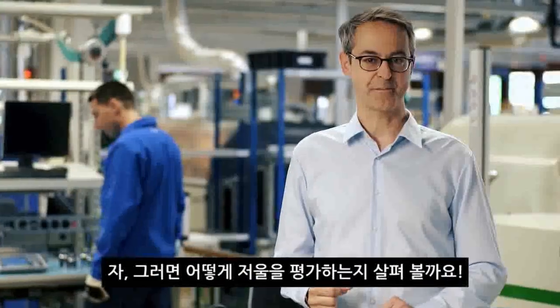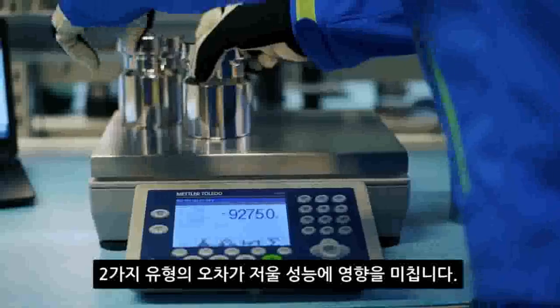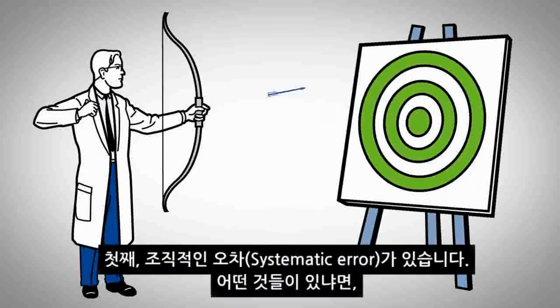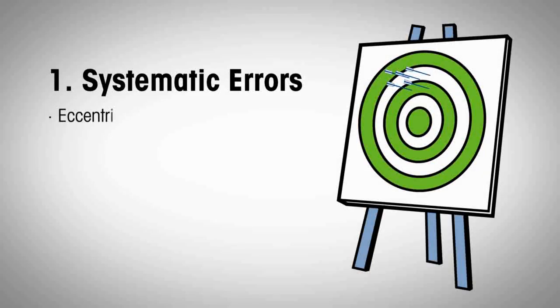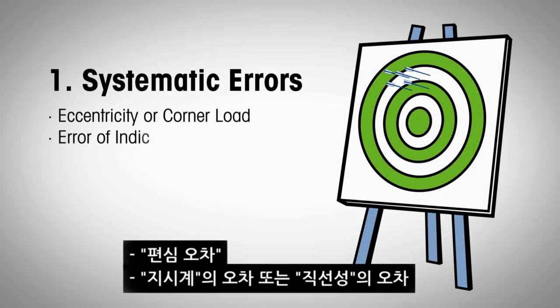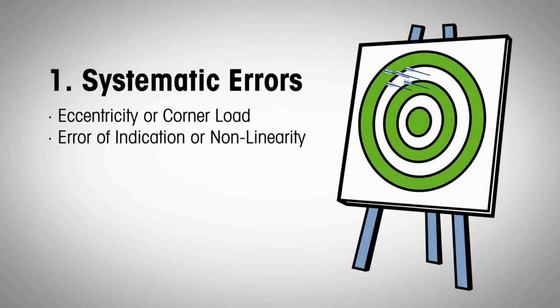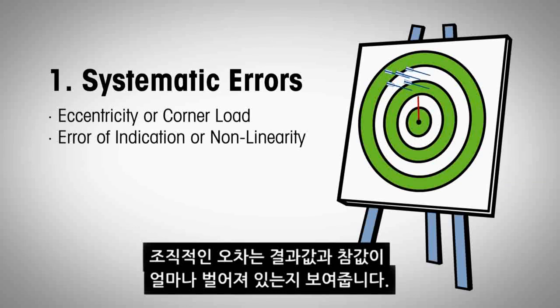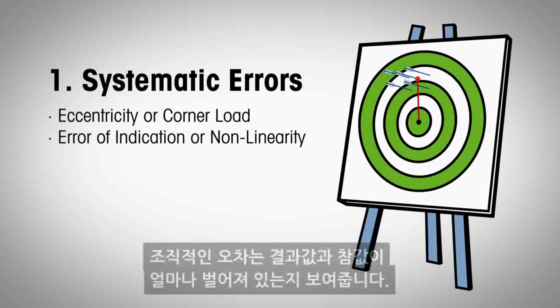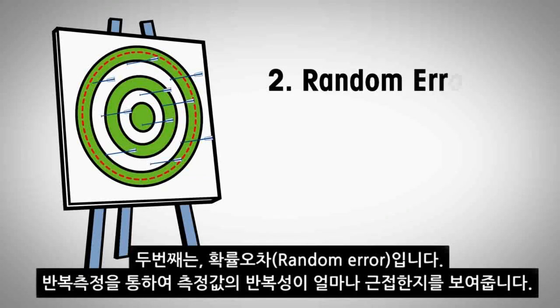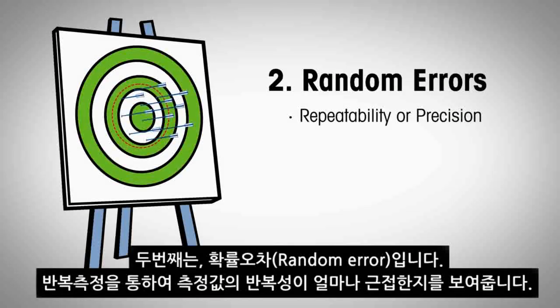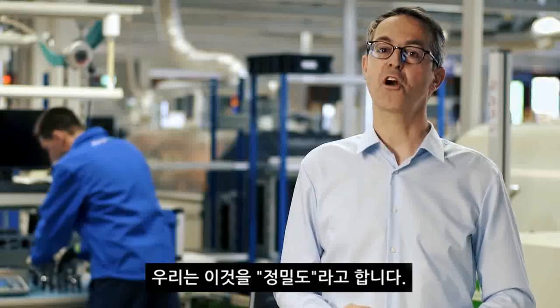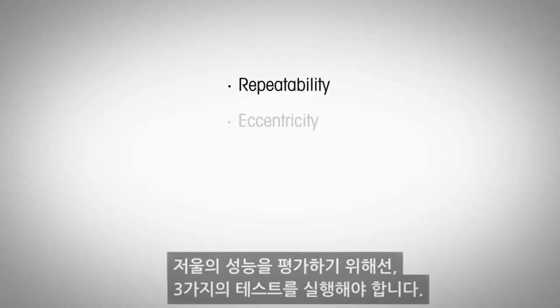Klaus mentioned the performance of weighing equipment. Let's have a look at how it is assessed. The performance of your weighing equipment is influenced by two types of errors. First, systematic errors, like eccentricity or corner load, and error of indication, which is also called nonlinearity. A systematic error shows you how far from the true value your result is. The second type is random errors, which is assessed by testing repeatability to tell you how close together a series of measurements is. This is also called precision. To assess the performance of a weighing device, all three parameters should be tested.